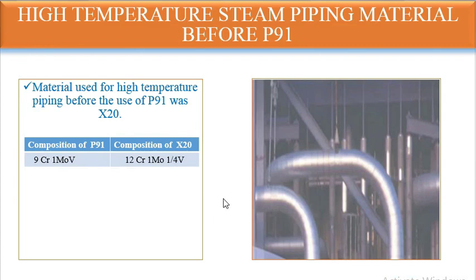Before P91, there was another material used for high-temperature steam piping called X20. X20 was the previous material; now it has been upgraded to P91. The composition of P91 is 9Cr1MoV, and the composition of X20 is 12Cr1Mo¼V. We are no longer using X20 — we are now using P91 material.